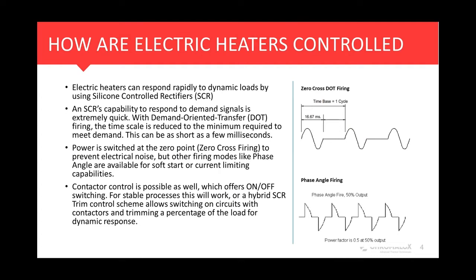You might see the term zero cross firing used. All that means is that power is turned on or off at that zero point of the AC sine wave. There are some other firing options available, namely phase angle, which lets you turn on or off anywhere along that AC sine wave. If you're at peak load, especially for a really large load, switching on that power can introduce a lot of harmonic distortion and noise on the line. So we typically only use phase angle for soft starts or current limiting, but it is another type of firing option available for electric heat.